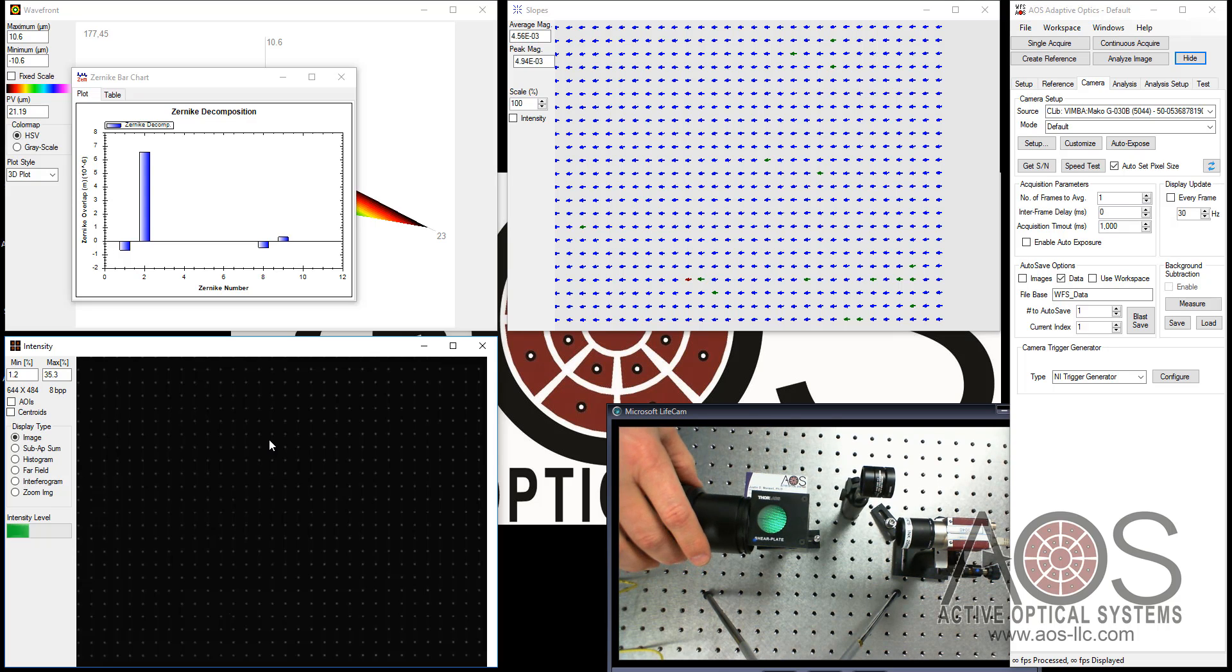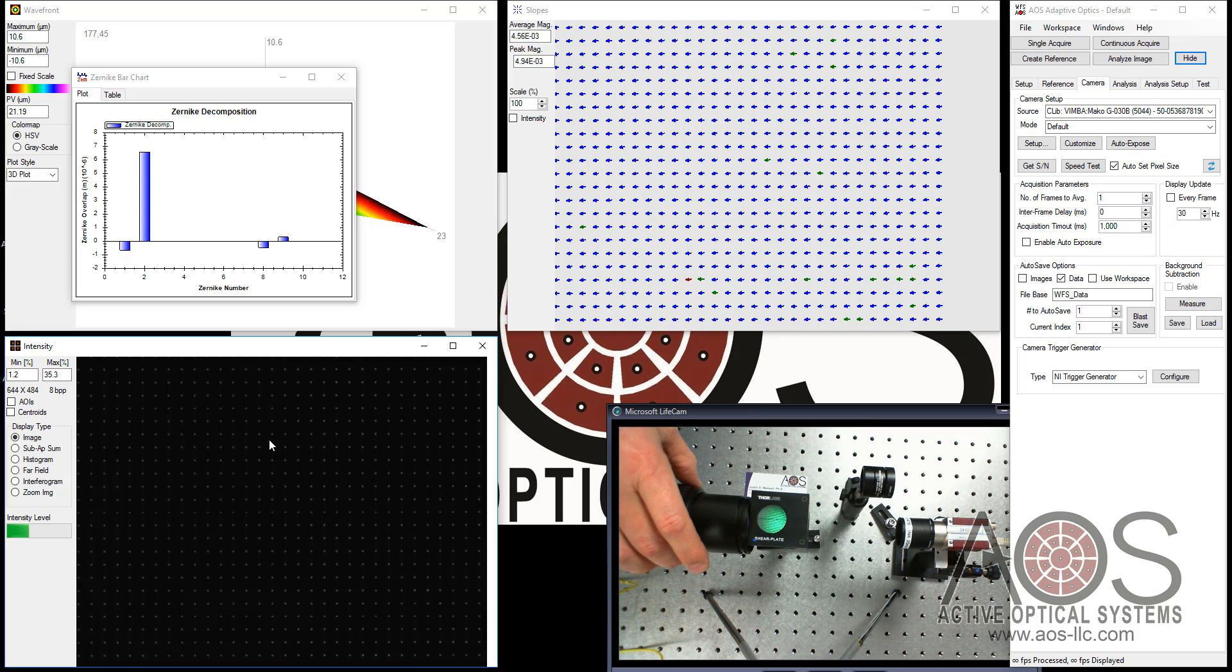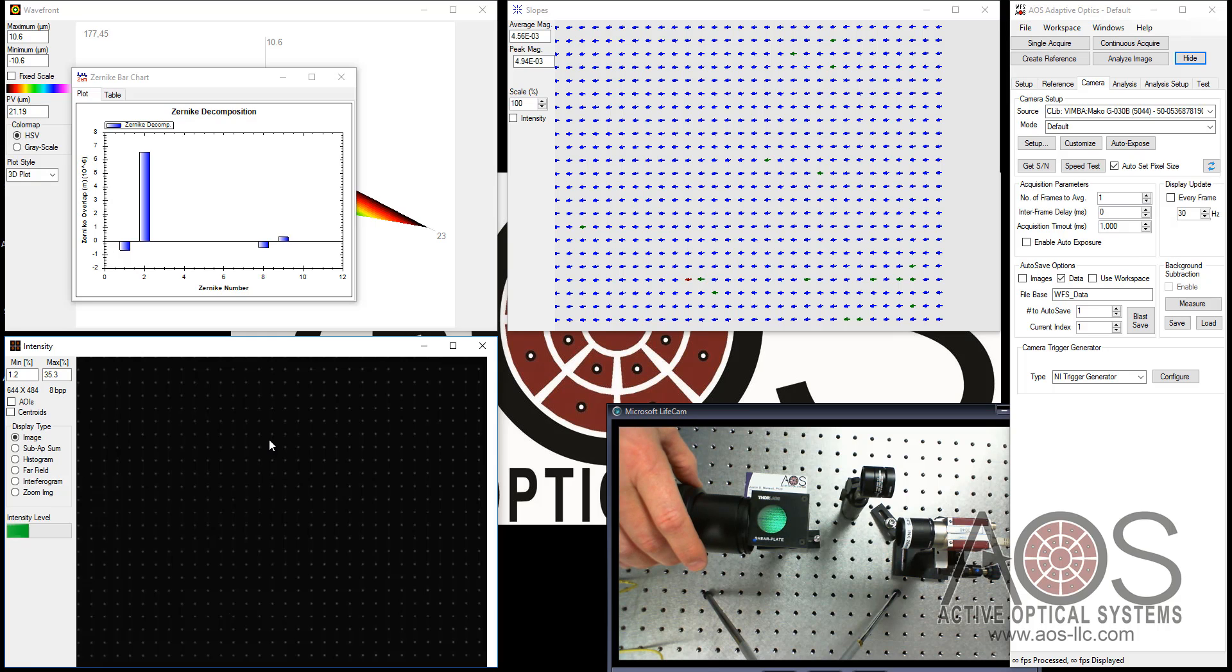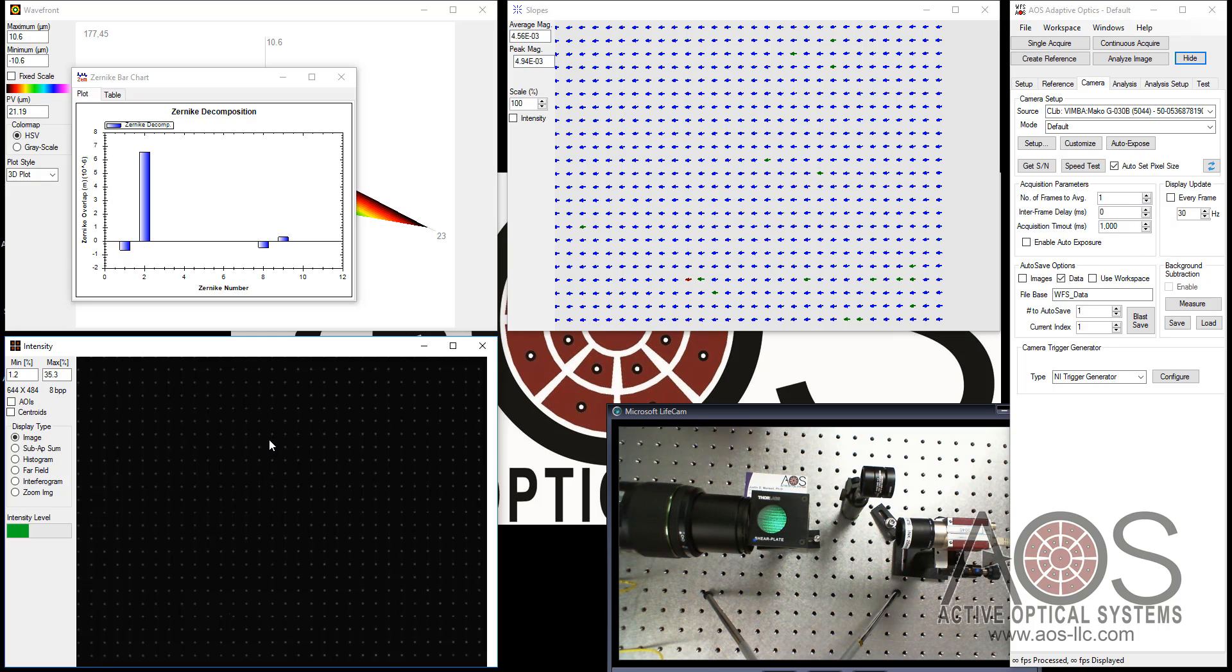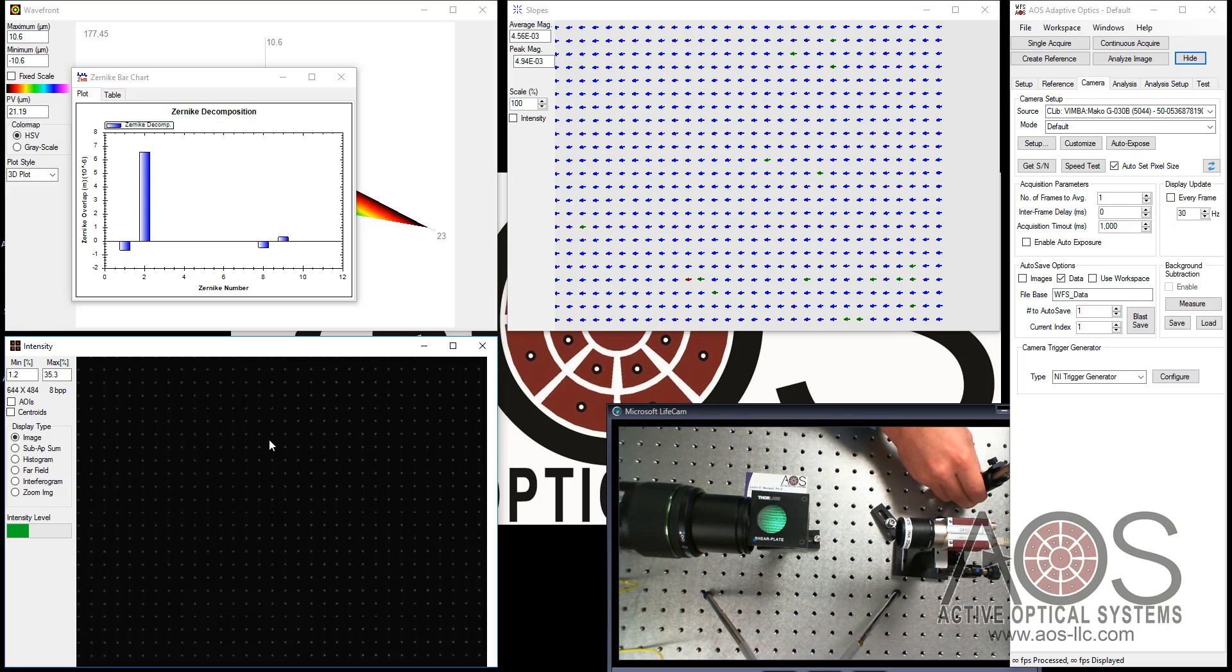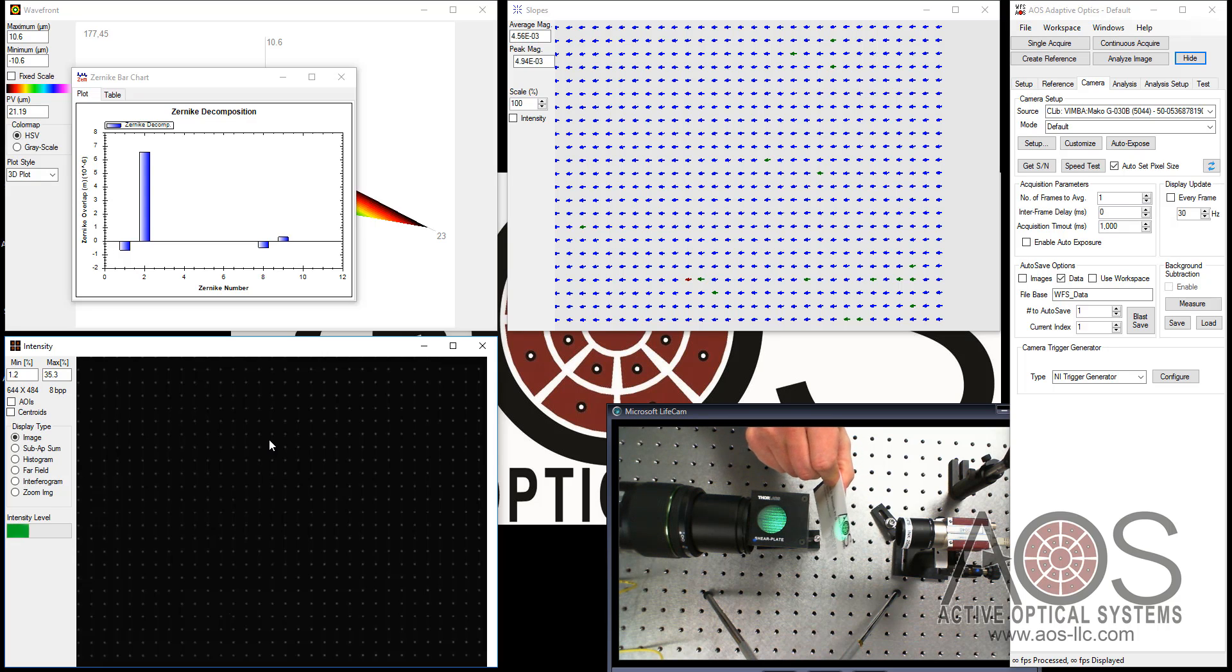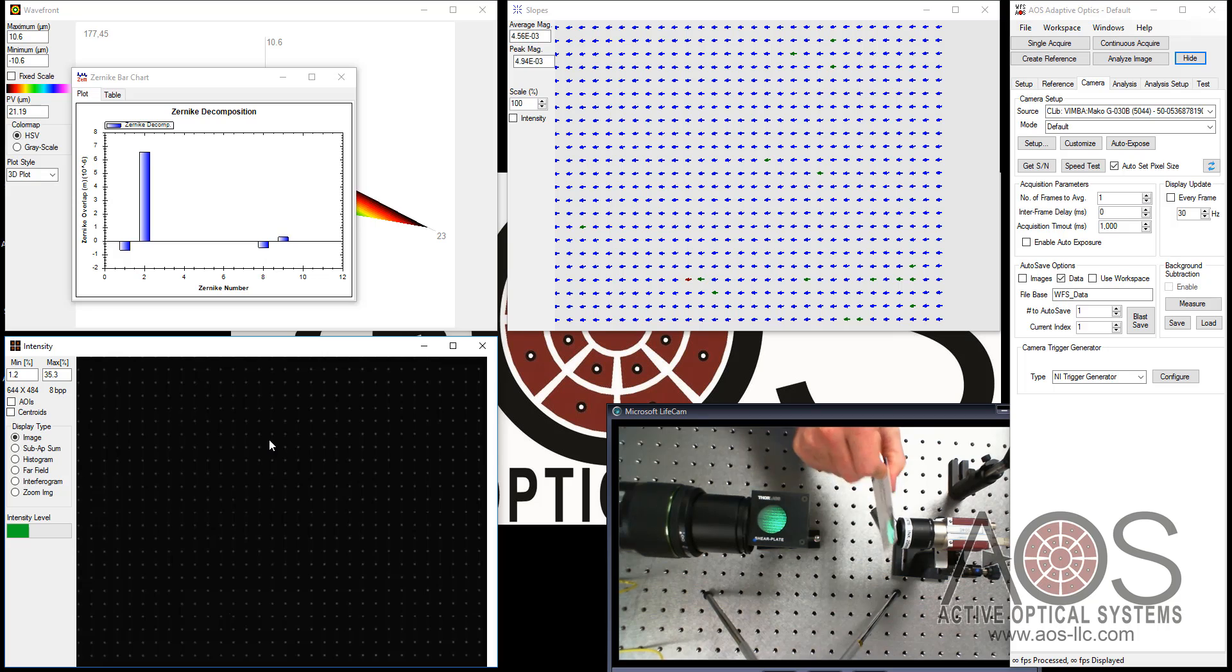Now you can see in the shear plate here an array of lines corresponding to collimation. What I can do is show you that I can adjust the collimation by adjusting this adjustment on the lens. I'll try to get it back to as close to collimated as I can. I have a lens assembly here that is sitting off to the side that we're not using. The light then is going through the shear plate and illuminating the lens array.